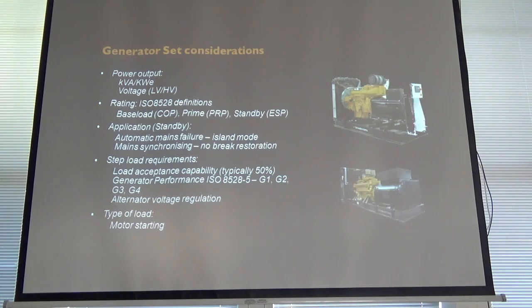But the point being, for any site that you've got, the key questions to ask are, how long do you ever expect it to run per year? Worst case, what is the real application? If it's a major hospital, you'll want a PRP rated set, prime rated set for a standby application. So I hope that gives you a rough idea.